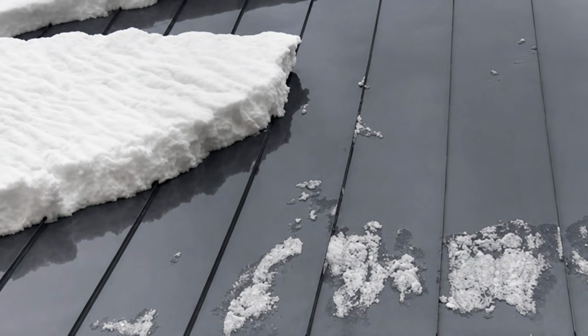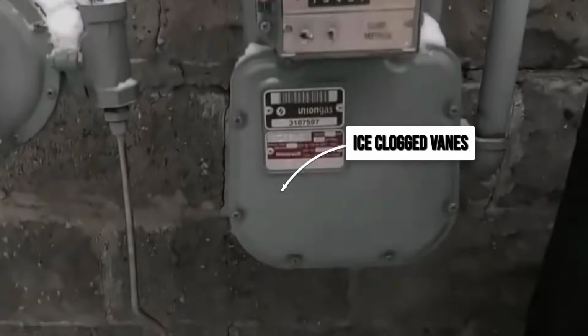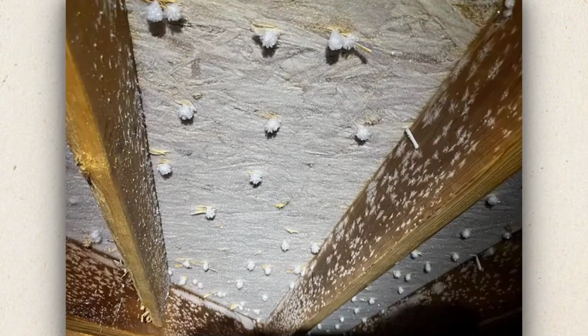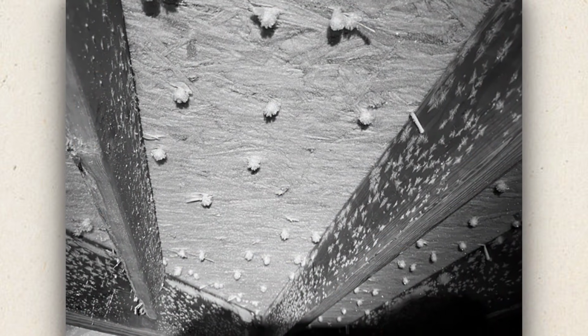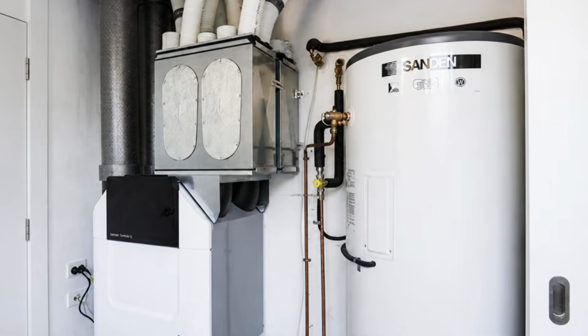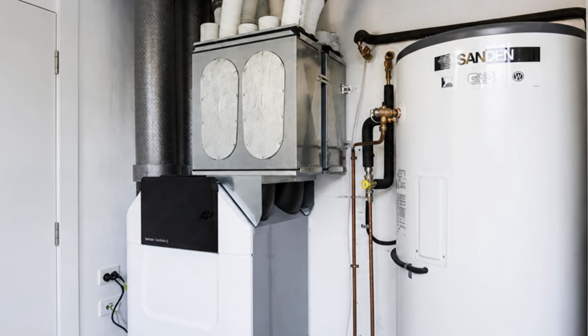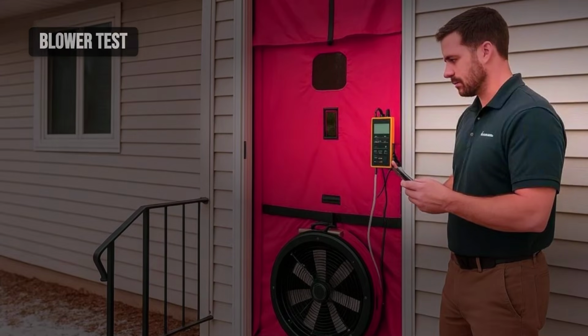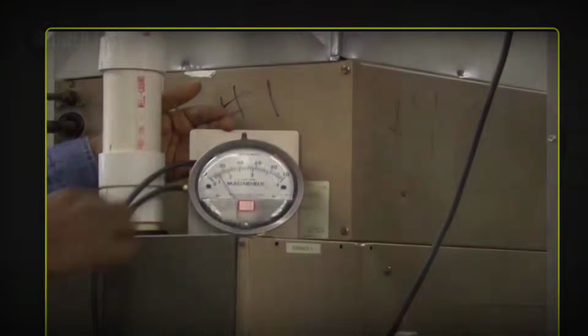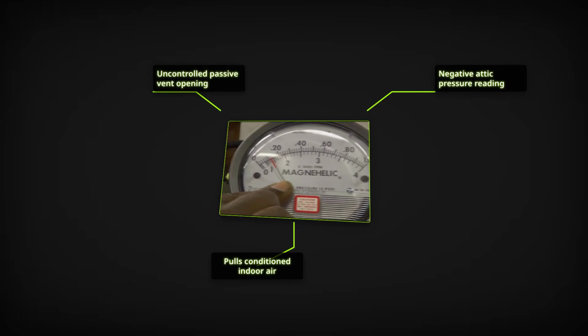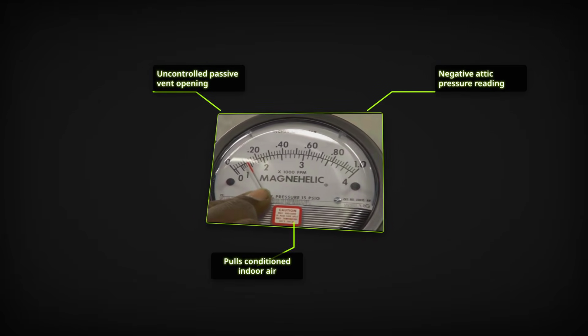But be honest about the other side. In a cold climate, attic moisture can freeze the vanes solid in winter, shutting the thing down exactly when you don't want a hole in your roof. And in a tight, modern, high-performance house where a mechanical system is already carefully managing every cubic foot of air exchange, punching an uncontrolled passive exhaust into the envelope can throw off the pressure balance the whole system was engineered around.